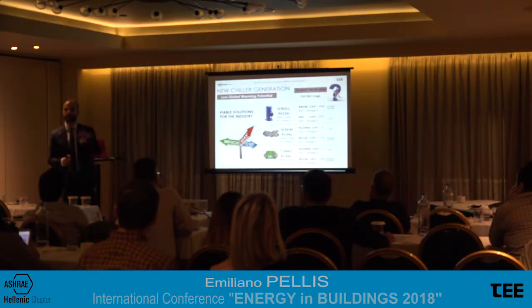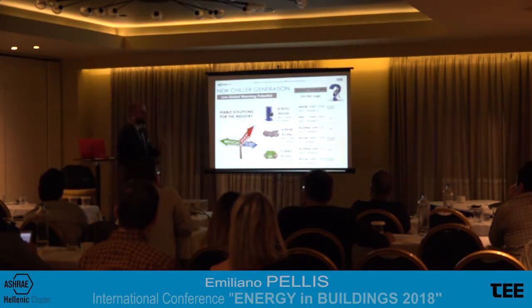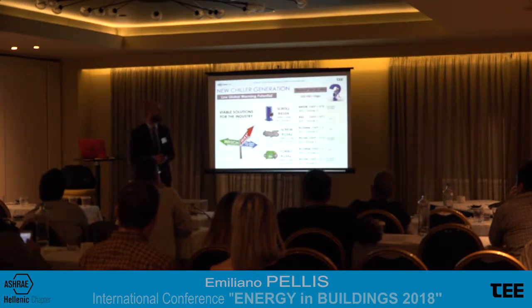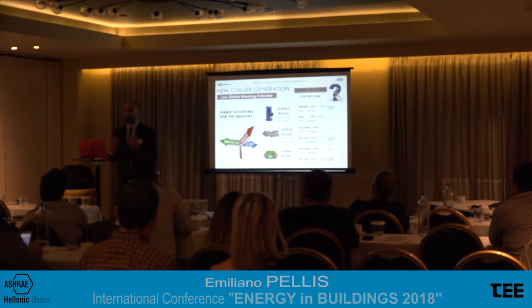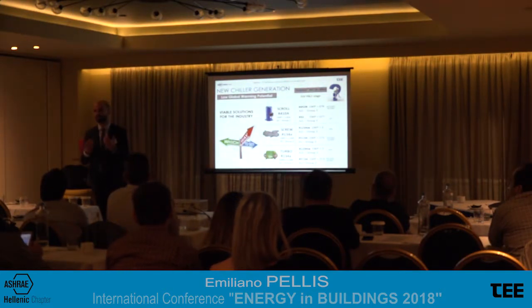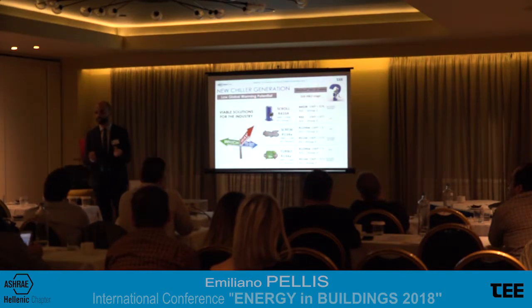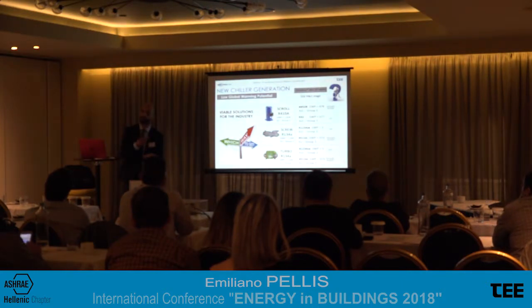this refrigerant provides a lower cooling capacity. I mean, if we take a unit with 134a and we fill the unit with the ze, instead of 1000 kilowatt, the unit will give us 700, 750 kilowatt. So we lose 20-25% in terms of cooling capacity, even if the efficiency is slightly better than 134a. It means that, from the side of all the chiller manufacturers, we have to completely redesign the unit in order to compensate the natural reduction in cooling capacity through an appropriate selection of compressor, of coils, of heat exchangers, of all the details.